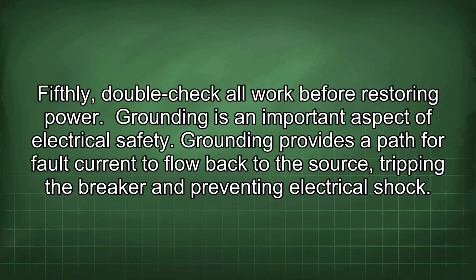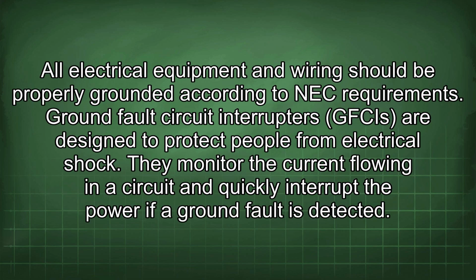Grounding is an important aspect of electrical safety. Grounding provides a path for fault current to flow back to the source, tripping the breaker and preventing electrical shock. All electrical equipment and wiring should be properly grounded according to NEC requirements.